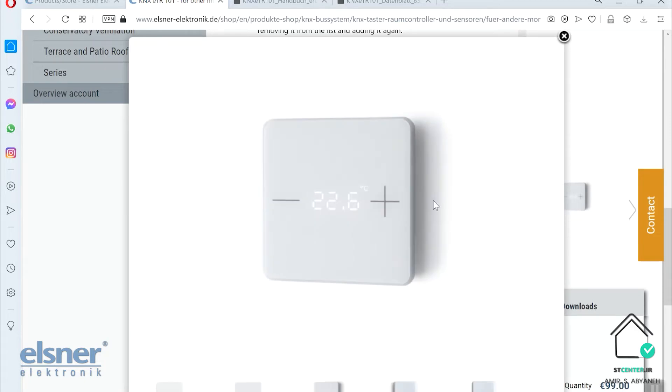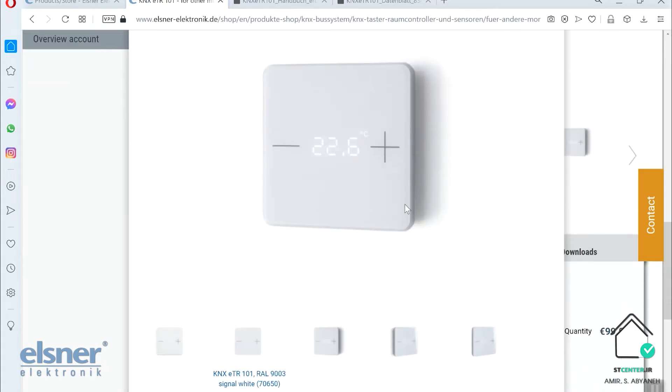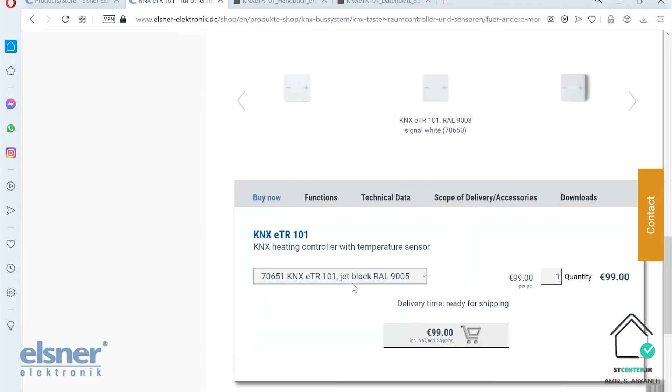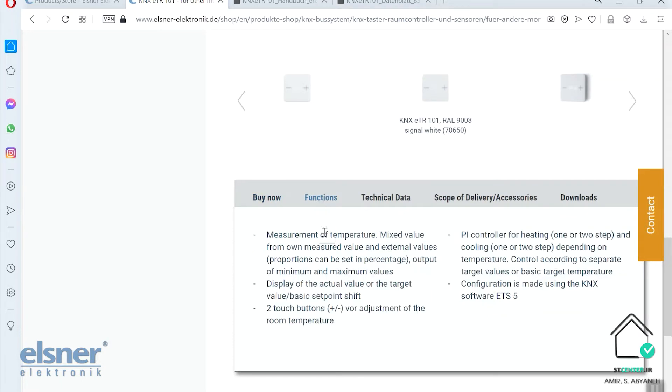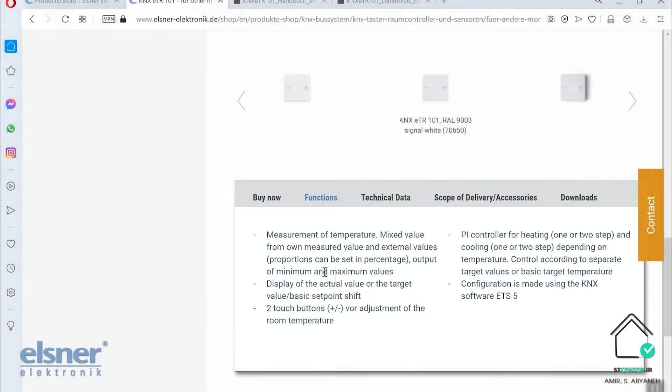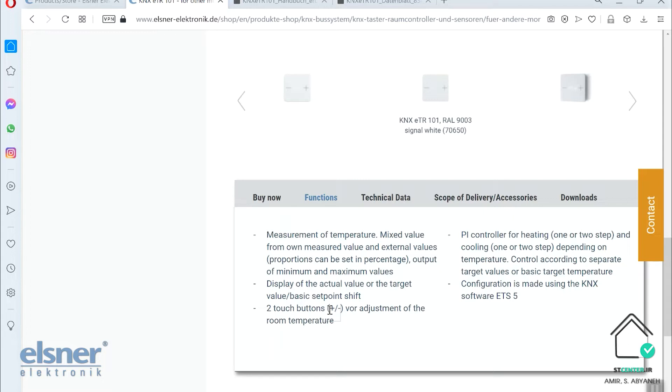You can see it is really a teeny tiny thermostat, so stylish in two colors white and black. About the function: it is going to measure the temperature and then control the room heating and cooling applications like floor heating, radiator, fan coil, electrical heating and so on. There are two touch buttons on it. You can increase or decrease the set point value. Also it shows you the current temperature of the room and the set point temperature. It is equipped with a proportional integral controller to control the system and make the control variable for actuators.